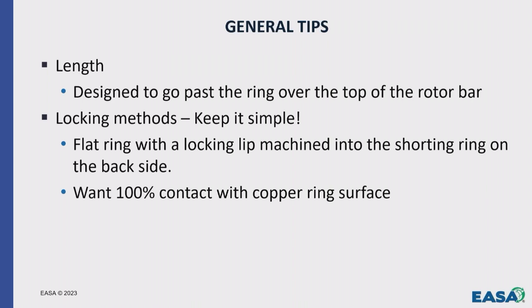The best way to handle a stainless steel ring, whether you're doing a new one or replacing it, is to keep it as simple as possible. I've seen copper rings where they'll cut a radial groove in the OD, and then they'll do a matching groove on the ID of the stainless steel ring. They'll try to heat it up, and they'll try to fit it in there, and it'll fall in there. But what happens is the more fits you have on a stainless steel ring where it connects to a copper ring, the greater the chance you have for shorting and arcing during starting.